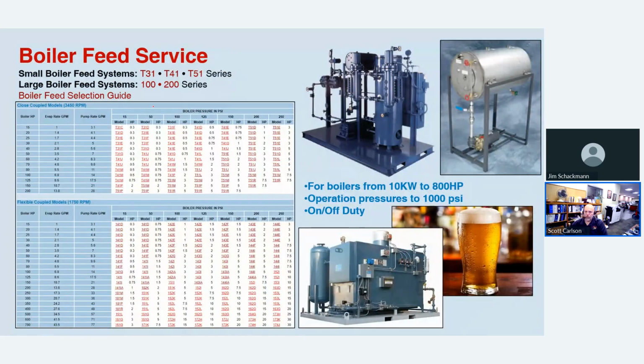So one of the first applications that regenerative turbine pumps were made for is boiler feed. That is where it all started. Because there are so many boiler systems and boiler feed systems that have come and gone through the years, different companies have manufactured them. Oftentimes, if you get into an older building where there's a boiler feed system, you'll look at the boiler feed pump and it's pretty much unrecognizable.